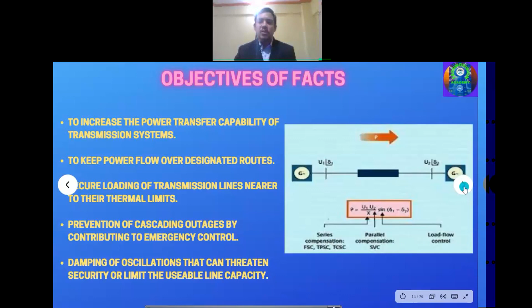Suppose I want to transmit 1500 megawatt power with the 400 kV double circuit lines. So I want near about 3 double circuit lines, each carrying 500 megawatt power. But when I implement FACTS device on that 400 kV line, only 2 lines will be sufficient to transmit 1500 megawatt power. Means 750 megawatt, again, we can divide into double circuit that power. So we can say that transmission cost can be minimized. Even the losses during transmission also can be minimized.